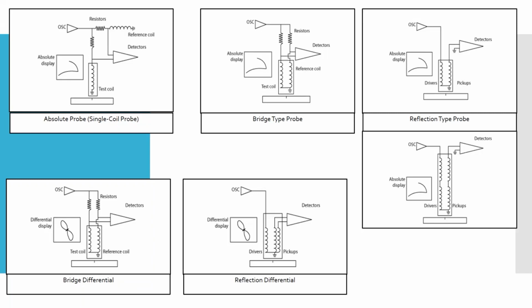You can see another coil type - another name for a differential coil is a bridge type probe. So the bridge type probe is also your differential coil, shown in the middle at the top. This is differential - it's showing those two coils, those two test coils that are kind of opposite.